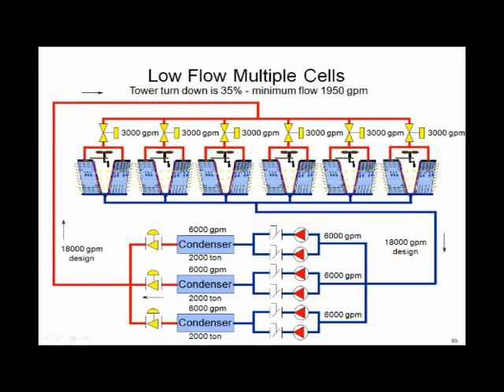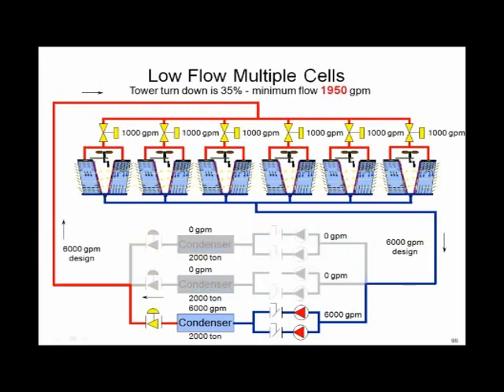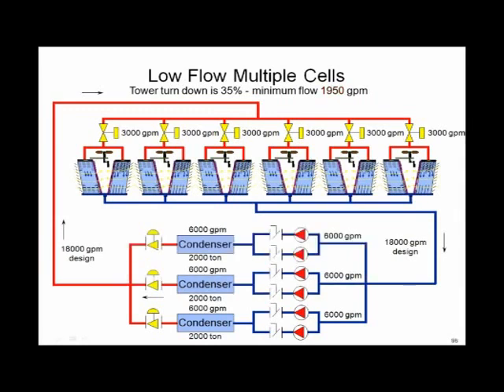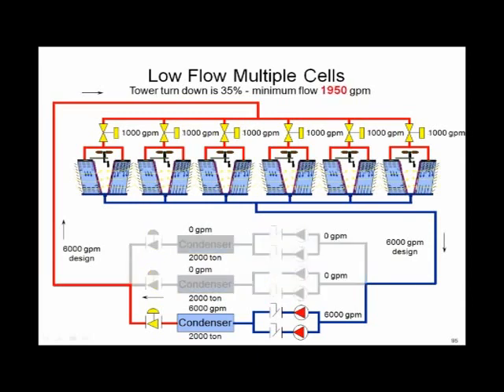So what did our guys find when they got to the job site? Take a quick look. Do you see what you've got right now? What did they find when they got there? Yep, that's what they found. They found 1 chiller running, the other 2 valved off, and all 6 cooling towers running. 6,000 tons worth of towers, nominal, on 1 2,000-ton chiller. And they couldn't maintain conditions. They couldn't keep the chiller online. Why? Wow, low flow. Are you telling me, Chris, there's only 1,000 GPM per tower? Correct. Minimum allowable was 1,950.